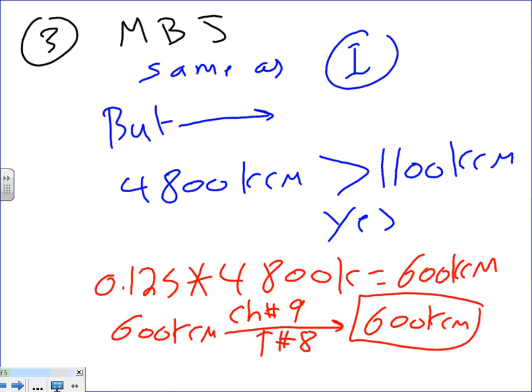Everybody knows how to go to chapter 9, table 8. Say, for example, Spencer, suppose I came up with 533.3 kcm. What the heck is 533 kcm? Which standard size? You take it to chapter 9, table 8, and that's where you find the standard conductor sizes that we use in this type of industry.